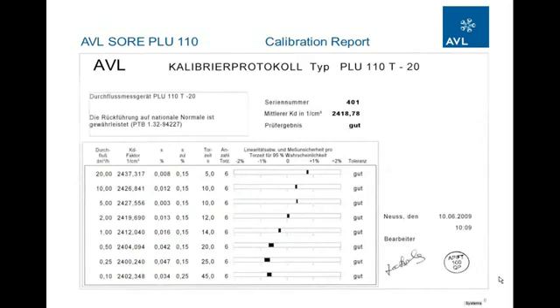This shows a typical calibration report of a PLU flow meter, and very important, this protocol shows that it is traceable to national standards. And what we do is we calibrate from the highest flow point to the lowest flow point. We look for the real pulses for 1 milliliter. And this shows the average KD factor, and you see the individual calibration factors. This makes a curve, and this is a systematic error of the meter and will not change over the lifetime. And if you use it in electronics, then you work with the according calibration factor, and then we do a linearization and bring every calibration point to the 0 line here.